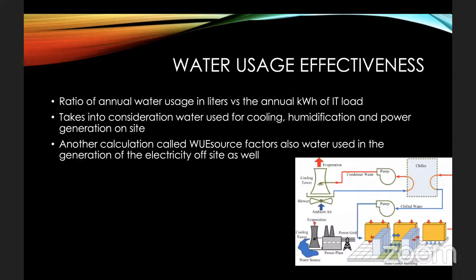So there is another data center metric called water usage effectiveness, or WUE, which was started by the Green Grid several years ago. This is a ratio of the annual water consumption versus the annual IT load. So it takes into consideration water used on site for cooling, air humidification, and on-site power generation. So the lower the WUE number, the less water that is used per kilowatt of IT load.